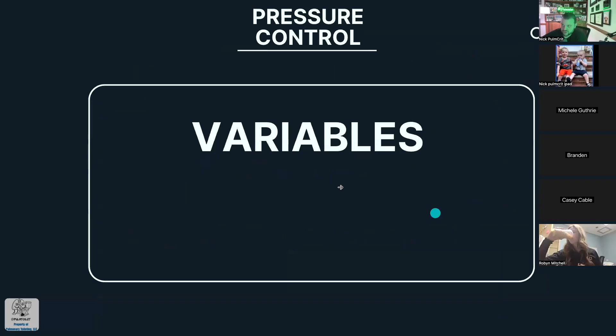So remember in pressure controlled modes, which includes things like PRVC, VC plus, autoflow, we set the inspiratory time. So you want it to be 0.5 seconds, 1 second, 0.7 seconds, 0.8 seconds. You're setting the inspiratory time in these modes. So one of the things that makes pressure control is that you're setting the I time. Now that might be a little confusing because on Servos for volume control, you set an I time. But if you look closely, you would see that the Servo spits out some flow number, because when you set an I time and you set a volume, the Servo just figures out a flow and then tells you it.